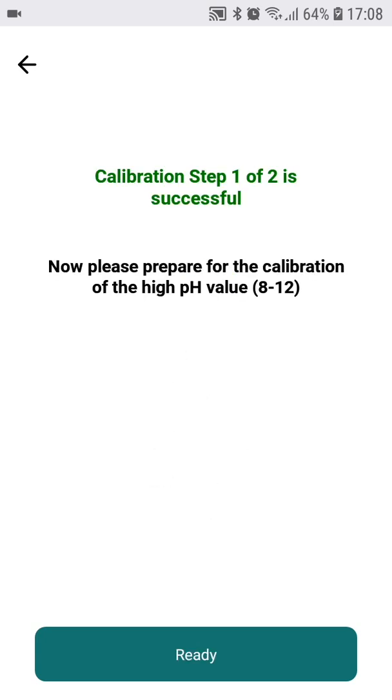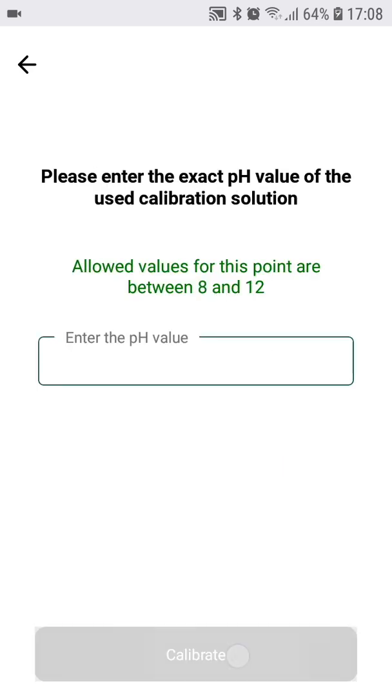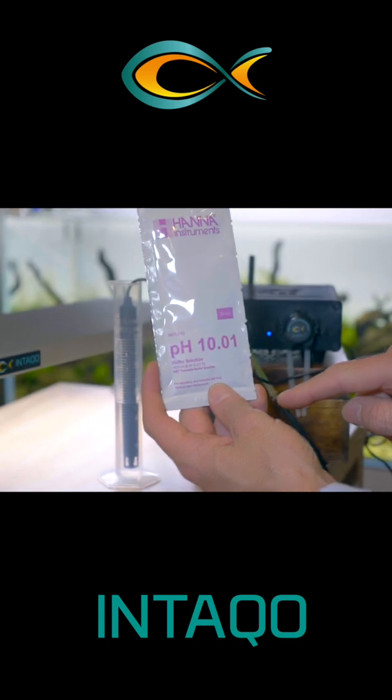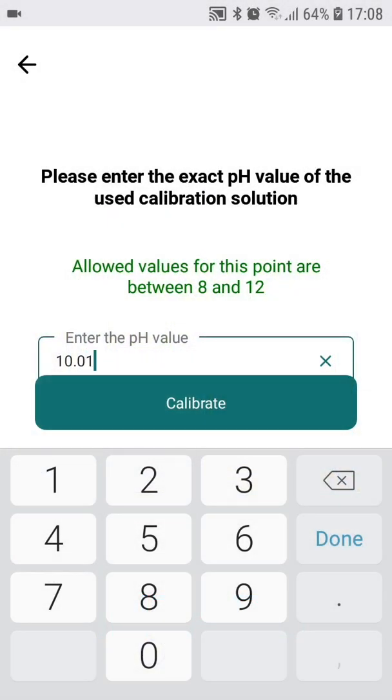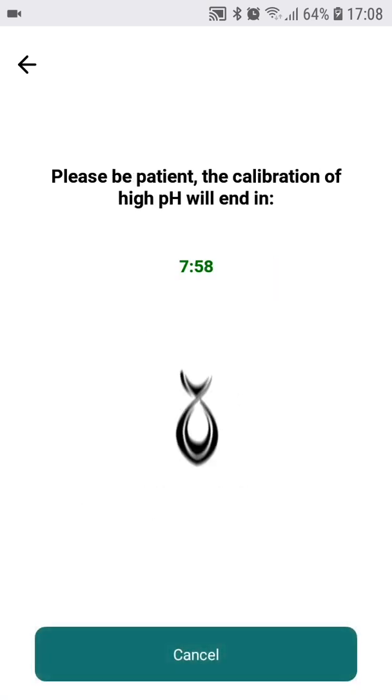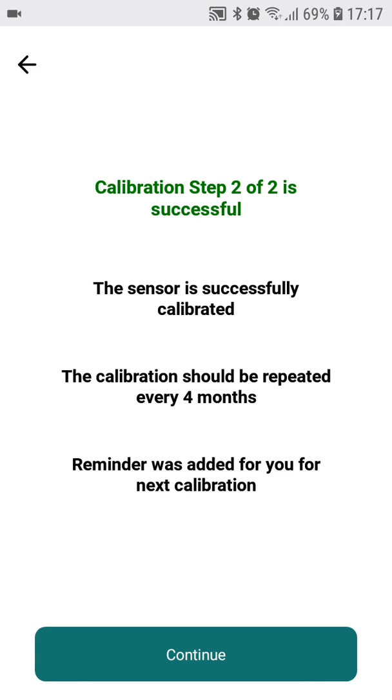After the probe is stabilized it automatically sets the low pH calibration point and we need to calibrate with the other calibration solution. When changing the calibration solution it is good to clean the probe in clean water. Next we need to make the calibration point on the high end of the pH scale. It will again take some minutes to stabilize. Luckily enough it is only needed to recalibrate the sensor about once in four to six months.